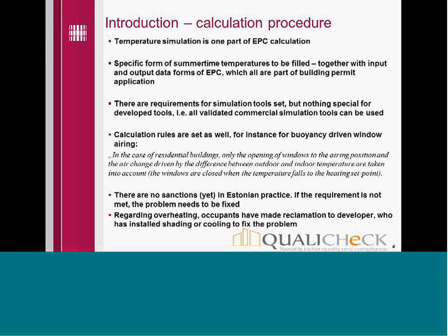So calculation rules are defined. For example, window airing can be taken into account with some limitations, like that the windows need to be in the opening positions, and wind-induced flows are not accounted, but only buoyancy-driven flows are accounted.